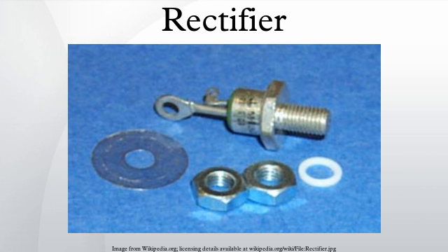For an uncontrolled three-phase bridge rectifier, 6 diodes are used, and the circuit again has a pulse number of 6. For this reason, it is also commonly referred to as a 6-pulse bridge. For low-power applications, double diodes in series, with the anode of the first diode connected to the cathode of the second, are manufactured as a single component for this purpose. Some commercially available double diodes have all 4 terminals available so the user can configure them for single-phase split supply use, half a bridge, or 3-phase rectifier.